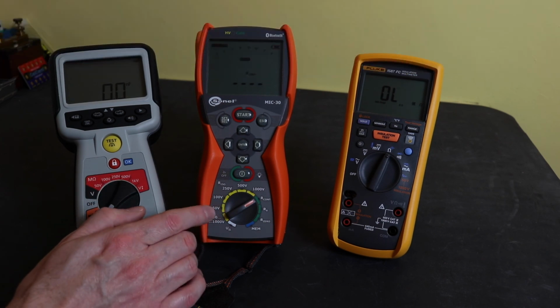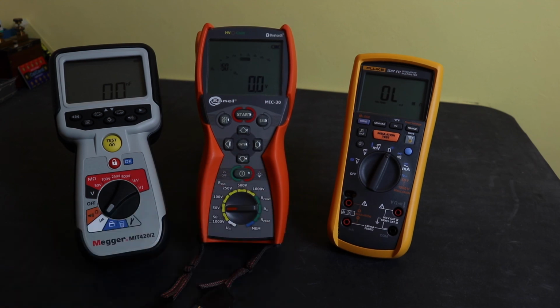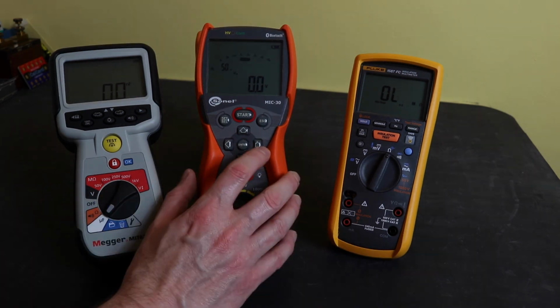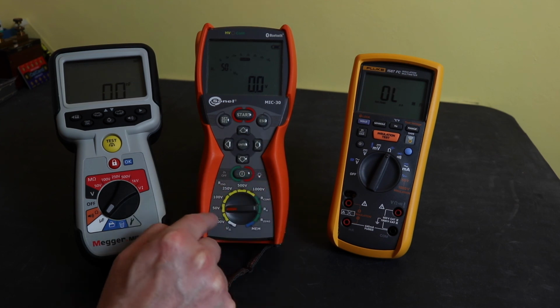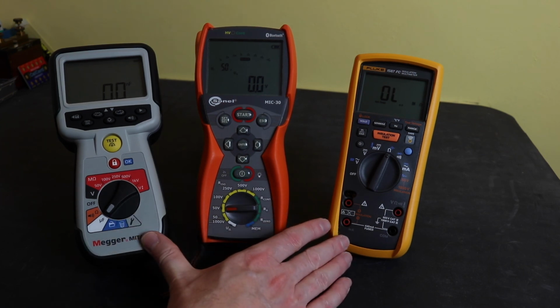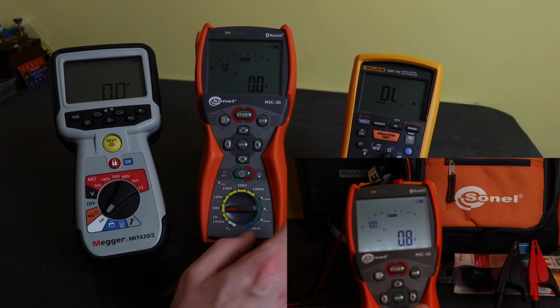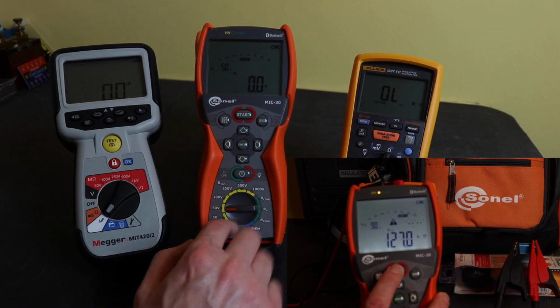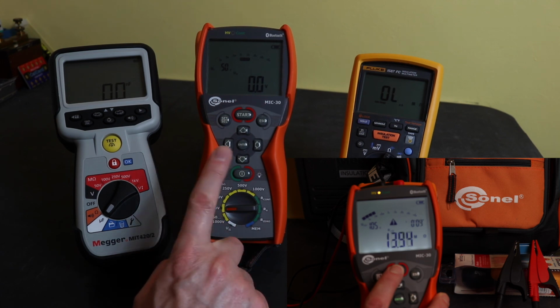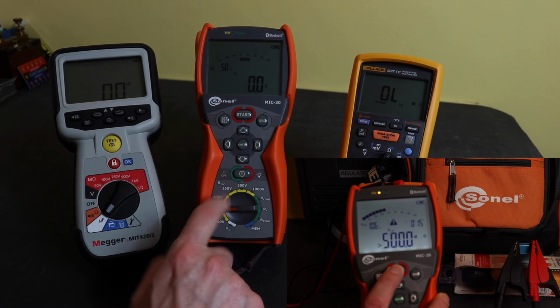However, it's a function built into the insulation test. So after you've done an insulation test, you can get a capacitance value out of it. That means that you are testing capacitance at a minimum of 50 volts, whereas these two instruments are a standard much lower test voltage for a capacitor. I guess if you're aiming this at electricians anyway, and capacitors on lighting circuits and motors, testing at 50 volts isn't an issue. However, the manufacturer doesn't give a tolerance for a 50 volt test, only gives a capacitance tolerance for a 100 volt test voltage and above. So really you need to be testing at 100 volts to do a capacitance test on this instrument.